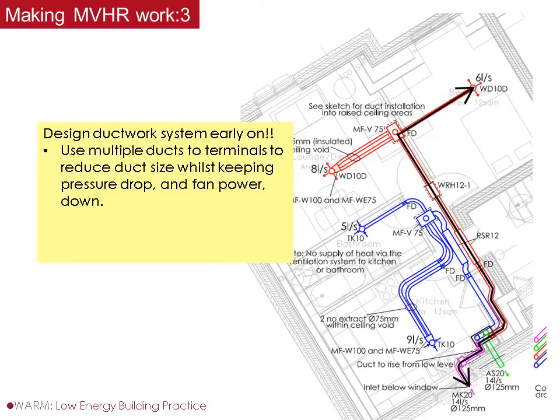This picture shows some small bore ducts, and you'll notice some are doubled up to go to certain terminals - these ones up here and down here, blue and red, have two ducts. Basically you need to make sure you're not increasing your fan power by squeezing in very small ducts. You need a generously sized duct - usually for domestic, that's 150 mil for your main run. This one here says 125.